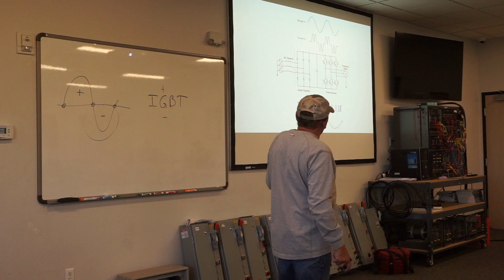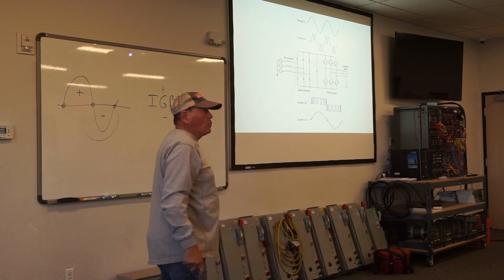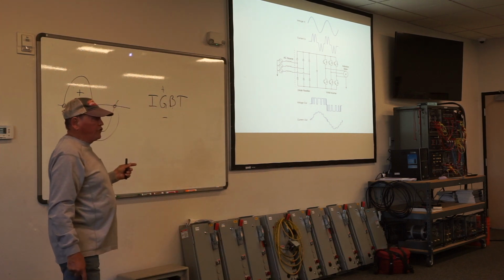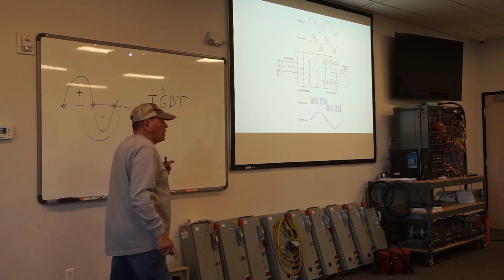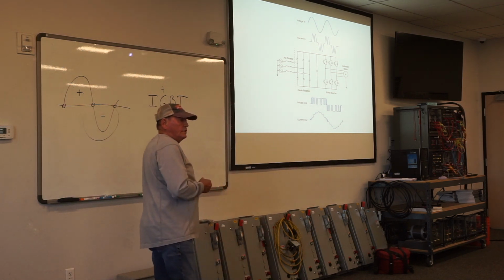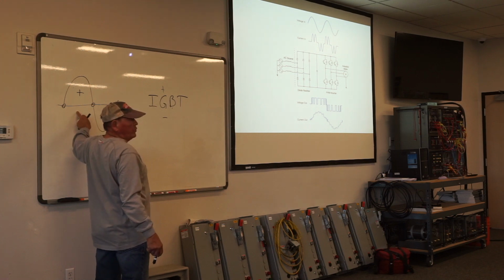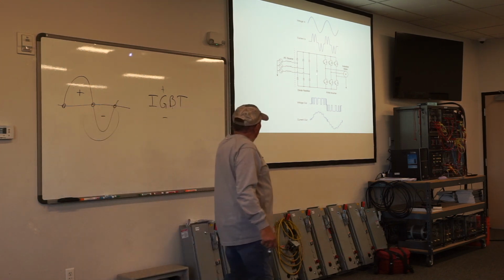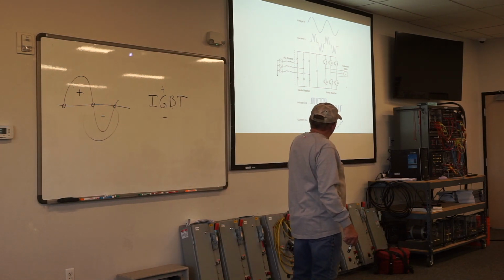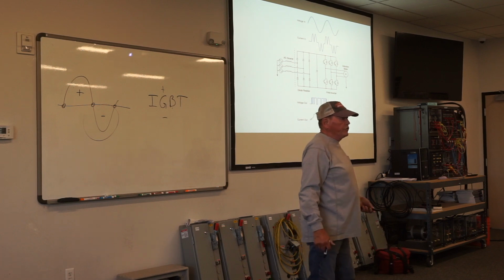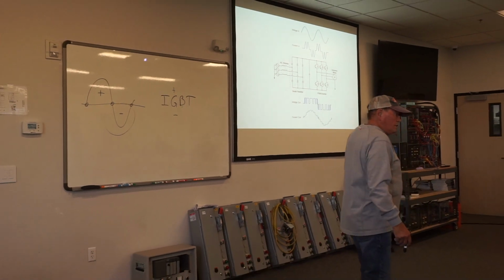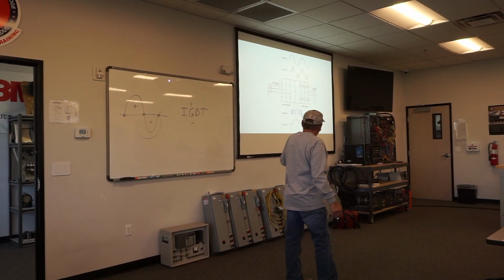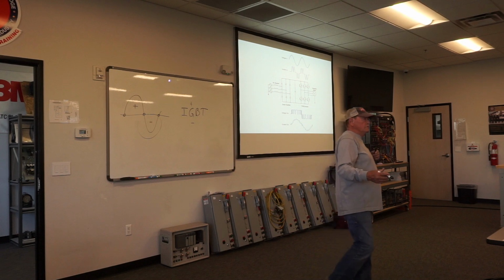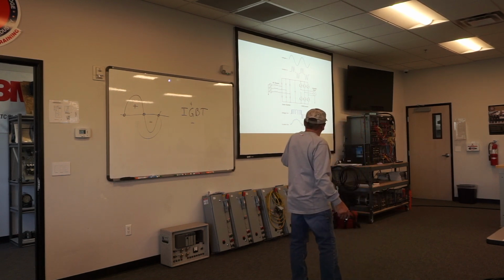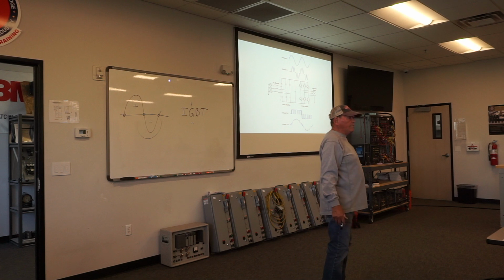So you can imagine how critical it is to monitor that zero crossing to tell which of those guys is supposed to fire. Now we're only looking at one phase. We're only looking at A phase, because B phase is going to happen 120 degrees later. So A phase IGBTs have nothing to do with B phase or C phase, because they're all 120 degrees out of phase with one another. So each one of these guys has a zero crossing 120 degrees apart. But these guys are very critical. This guy has to shut off before this guy turns on, because if they're on at the same time, I'm going to blow something up.